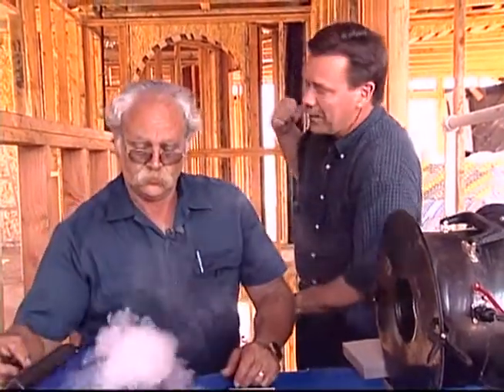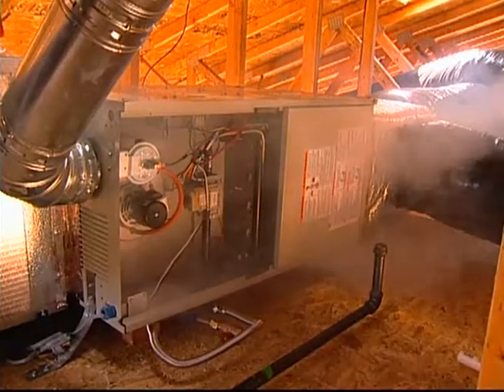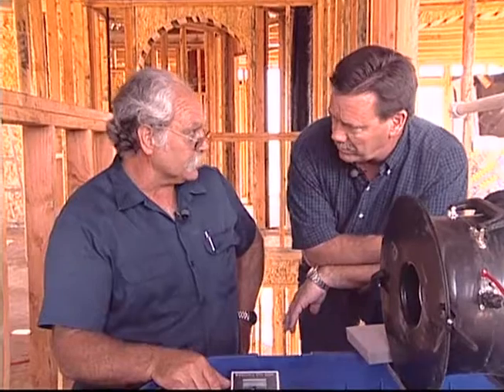There's also quite a bit leaking out of the unit itself — the furnace. Now, there's not much the builder can do about that — no, because the HVAC contractor just has to spend some additional attention sealing up the equipment as it comes from the factory. Where else do you find leaks? All over throughout the system — it just depends on if the installer made a mistake or maybe needs a little bit of training on how to put their components together. Well, thank you, Scott. Appreciate you being with us today.